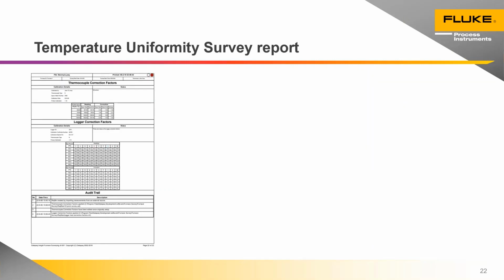Page 22 of the temperature uniformity survey report has the thermocouple correction factors, the logger correction factors, and the audit trail. Three very important items when it comes to auditing what you did, in that you can check here or prove that it was done with a logger that was in calibration, that you applied the correction factors to the reading, and that you applied the correct ones.